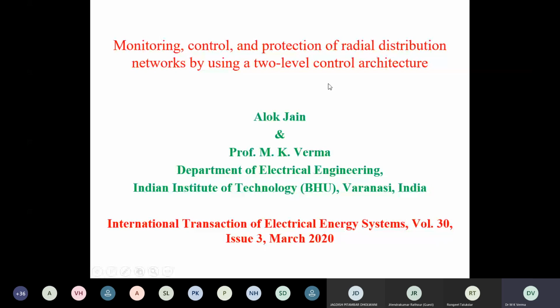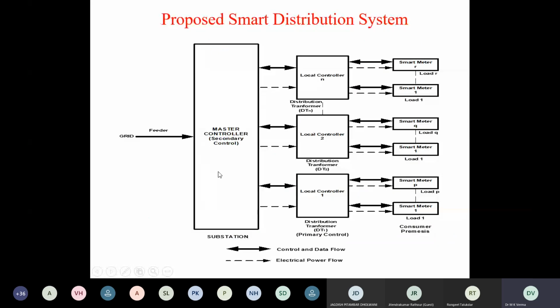So he had designed a smart distribution system where this is the main substation, where the master controller is, which is providing secondary control. This substation is getting power from the grid, and this master controller is linked to the local controllers. These local controllers are put at different distribution transformers, and the master controller is linked to the local controllers in bidirectional fashion. Now, smart meters are put at consumer premises, and all the smart meters in a particular area, which is supplied by this distribution transformer, are connected to the local controller in bidirectional manner.